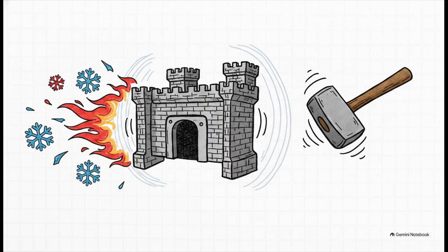To guarantee these safety circuits don't get thrown off by wild temperature swings or microscopic vibrations, the design strictly locks in the use of Class 1 C0G capacitors. And yes, I know that sounds like a droid from Star Wars, but these components are incredible. Made with calcium zirconate, they have basically a zero temperature coefficient. That means the performance doesn't change whether it's negative 55 or a blistering 155 degrees Celsius. And crucially, they have zero piezoelectric effect, meaning physical vibration will not accidentally generate false electrical noise. They pair these up with ultra-precise resistors just to ensure the defense system's calibration is absolutely flawless.